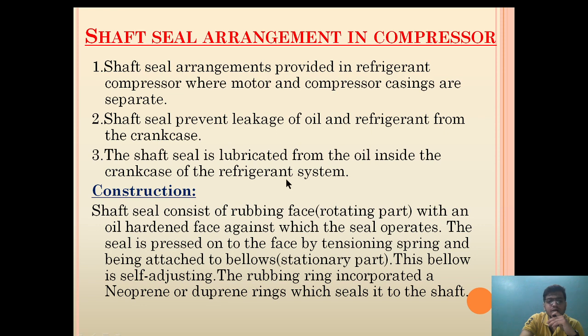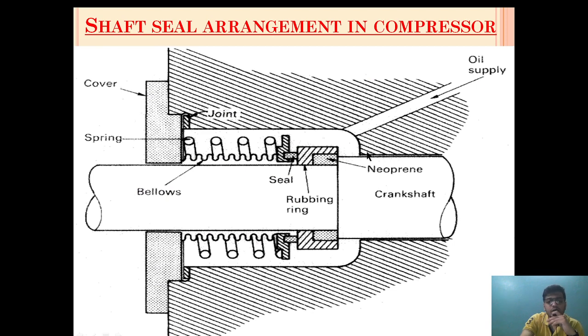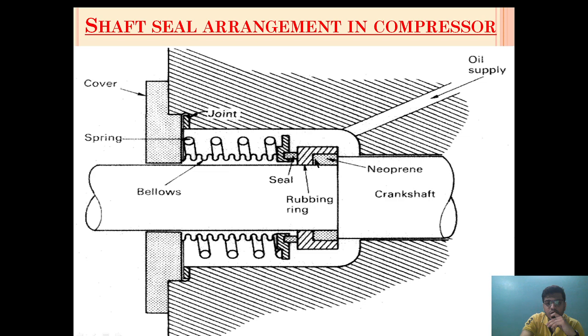The shaft seal is lubricated from the oil inside the crankcase of the refrigeration system. As you can see, this is the crankshaft side where the piston and compression take place, and this is the motor drive side where the motor is attached. This is a self-adjusting spring bellow which has a hardened face that is put onto the rubbing face, which is rotating in nature.